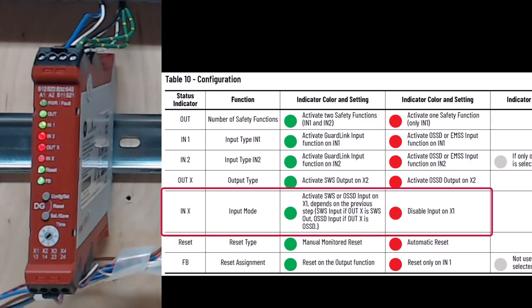The in X LED is flashing red, because you do not want to use the X1 terminal as an OSSD input. You would change it to green if you wanted to enable the X1 input. Keep in mind that the X1 input will always match the type of signal configured for out X. Both would either be OSSD or single wire safety. Short press the select button while the color is red to disable the in X signal.